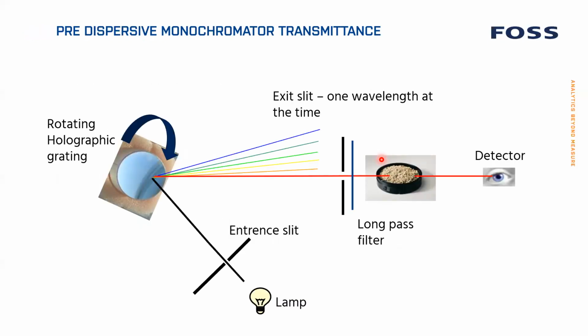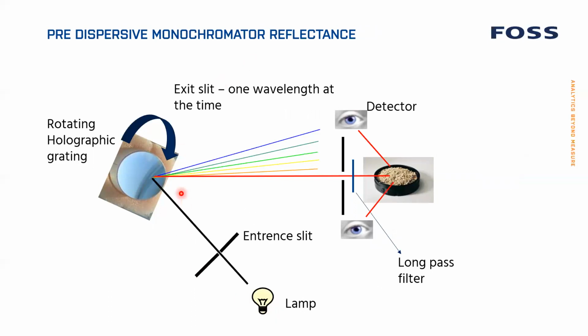So if we start with an Infratech, a Food Scan, it is a predispersive monochromator in transmittance. So the predispersive means that it splits up the light first. So you have a lamp, an entrance slit, a grating. The grating splits up the light in the different wavelengths. It goes through the sample and hits a detector. And as the grating moves, you will have different wavelengths coming through the sample. So it scans one wavelength at a time. This is then the typical setup we have for the Infratechs, but also for the DS2500L. And then we have the reflectance, which looks in the same way. You have a lamp, an entrance slit, a grating that splits up the light in the different wavelengths. It hits the sample, but then we look at the reflected light instead. Principles are very much the same.